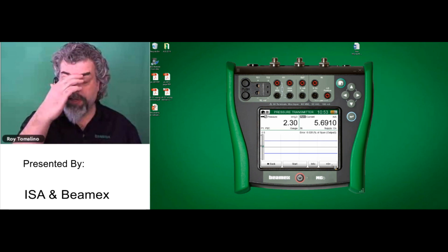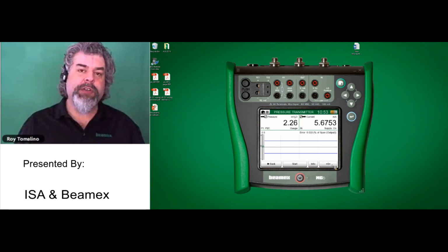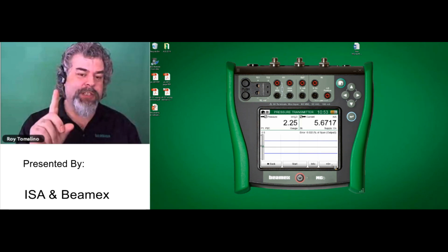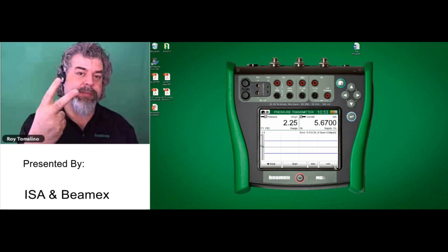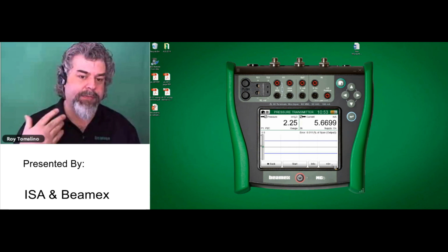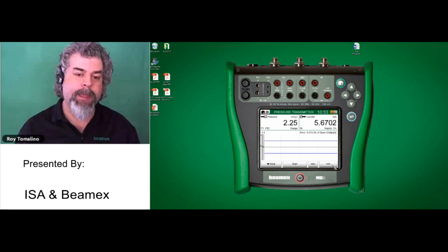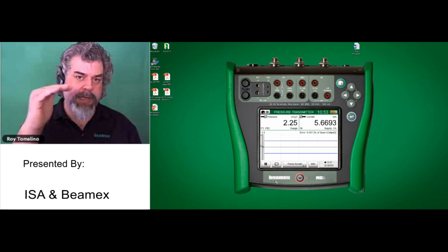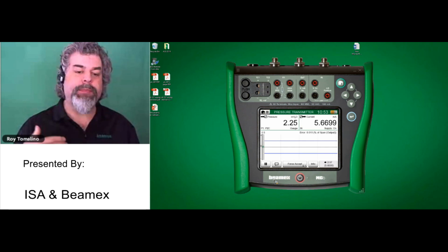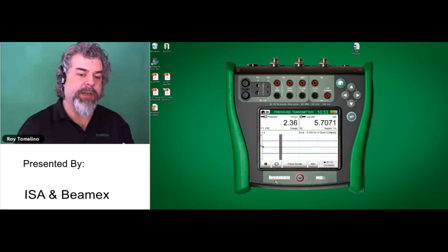And I overshot it a little bit. As Rich mentioned earlier, in my first test I only had 1 digit of resolution on that 300 PSI. On this 30 PSI, I have an additional digit, so now I have 2 decimals of resolution. And here's 2.25. Okay, let me hit start. Once it stabilizes, I've got it set to automatically grab the next test point, and that's what you're seeing here.